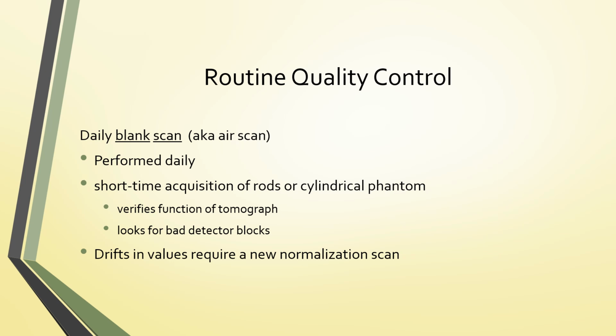Is the camera going to work for us today? And so one of the main things that we're looking for there is to make sure there's no detector blocks that are bad and make sure that the instrument's okay to use for the day. So that's the purpose of the daily blank scan. And if you see a lot of drifts in the values on the blank scan, then it means that your scanner requires a new normalization study.